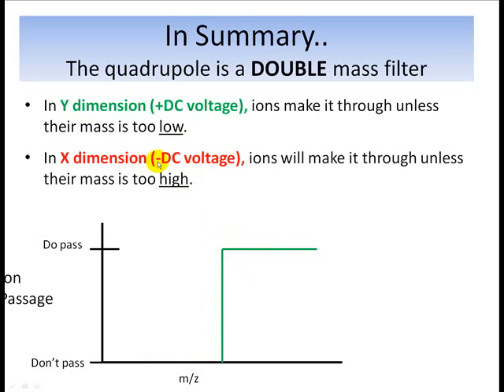You know, you have the second dimension. And in the x dimension, which carries on the rods the negative DC voltage, ions traveling down through the quadrupole will make it through unless their mass is too high, as we described. So the filtering function for that x dimension would look like this. Ions make it through up to a certain critical point in mass charge ratio. Anything above that, ions do not make it through.